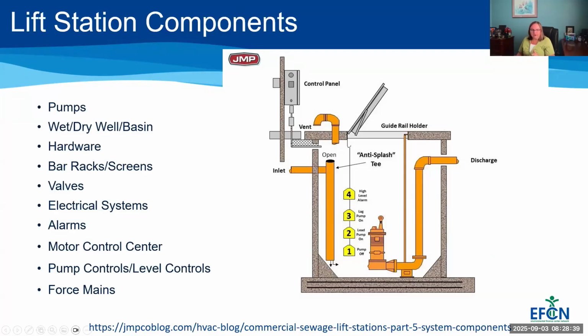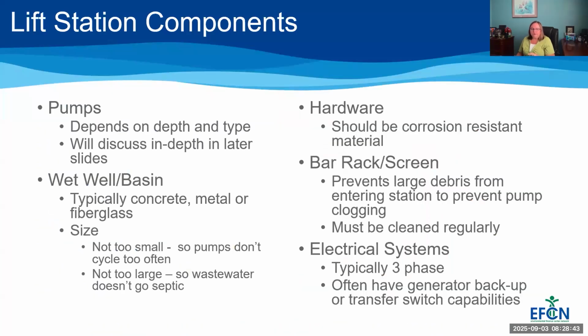So let's take a look at these components in a bit more detail. So the first thing in the lift station, probably the most important component, is the pump. And the pump depends on the depth of the lift station and the type of fluid that you're pumping. But in the case of wastewater, you're going to have probably just one of two types of pumps. And we're going to talk about that a bit more later in depth in these slides. And then your wet well or your basin, they're typically concrete.